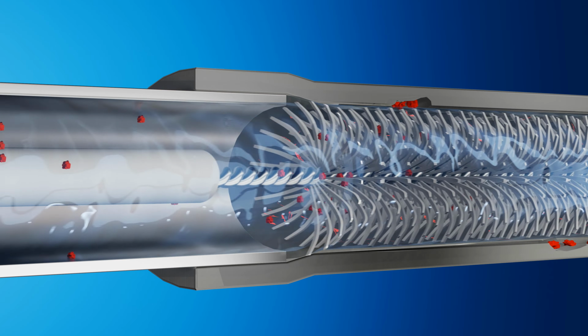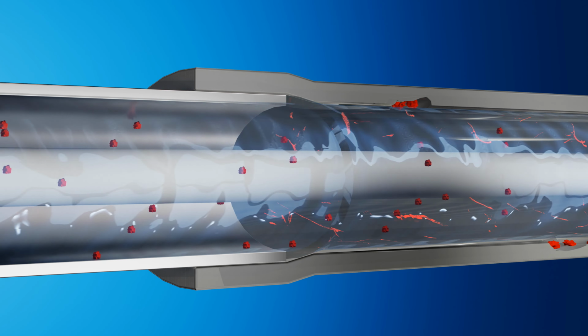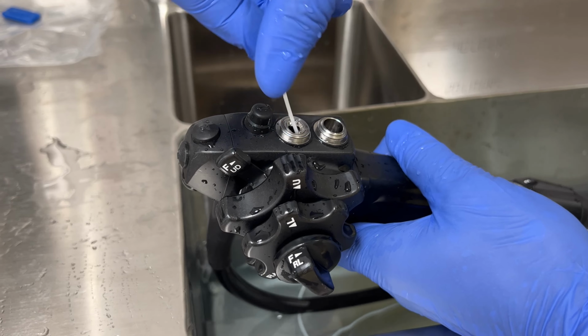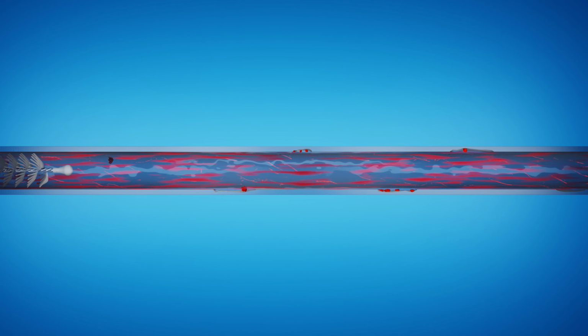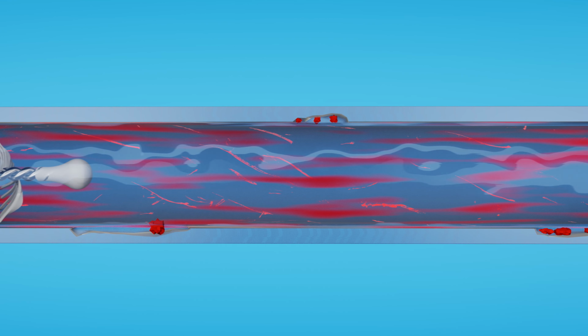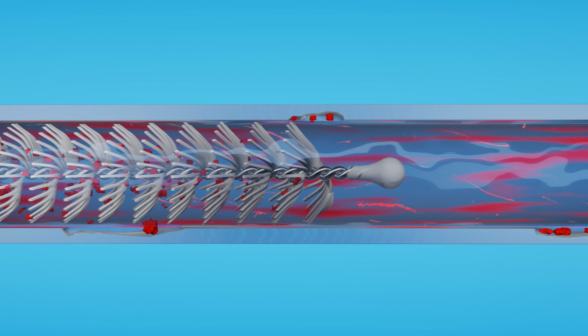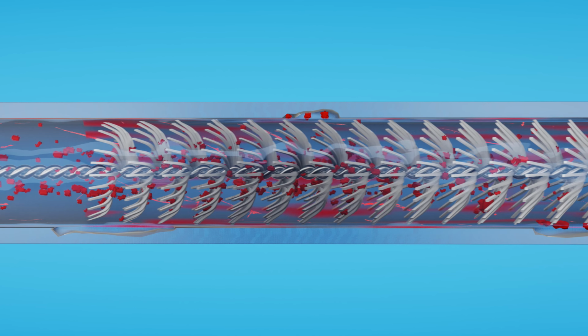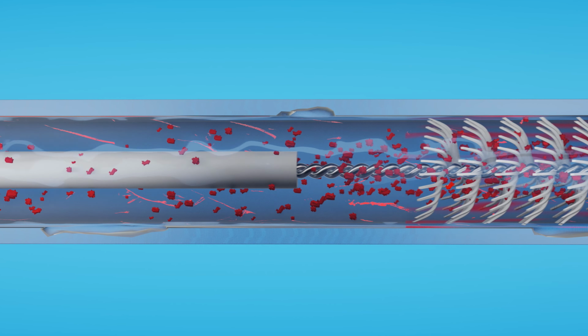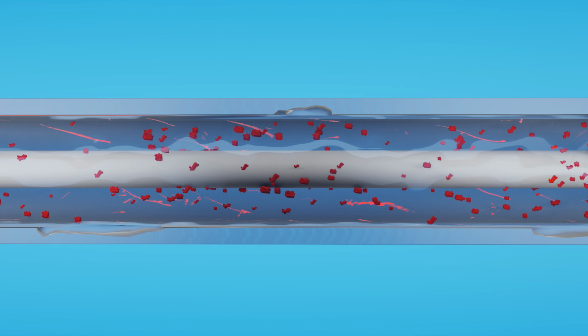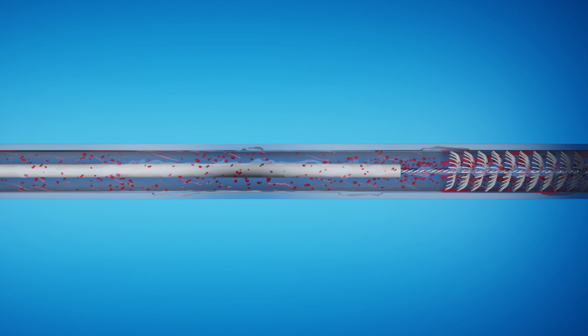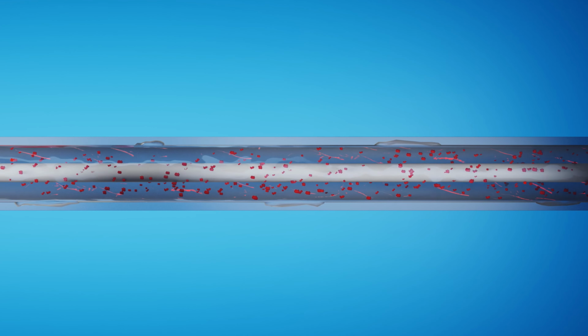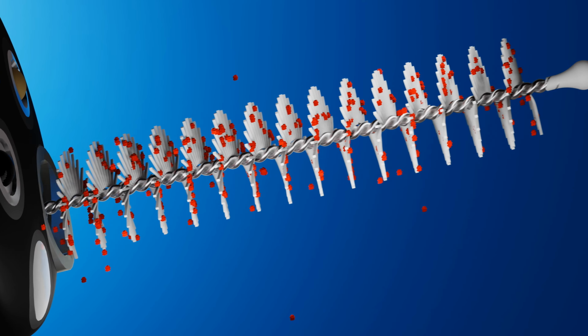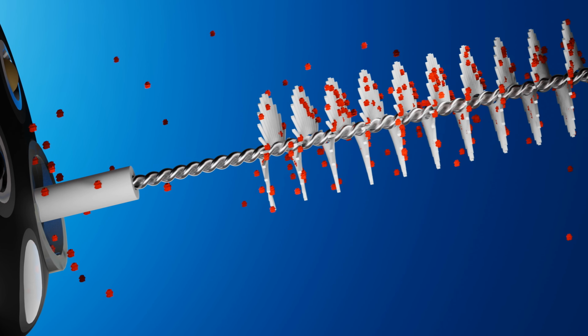Once the tube junction area is brushed and clean, the leading brush is advanced through the channel in short strokes of the flexible catheter. The leading brush travels through the channel, efficiently dislodging debris from the channel's wall, leaving it suspended in the enzymatic detergent solution present in the channel. As the leading brush exits the endoscope, it expels some of the debris from the channel into the wash sink filled with the enzymatic detergent solution.